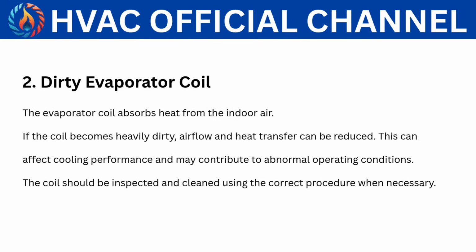2. Dirty evaporator coil. The evaporator coil absorbs heat from the indoor air. If the coil becomes heavily dirty, airflow and heat transfer can be reduced. This can affect cooling performance and may contribute to abnormal operating conditions. The coil should be inspected and cleaned using the correct procedure when necessary.